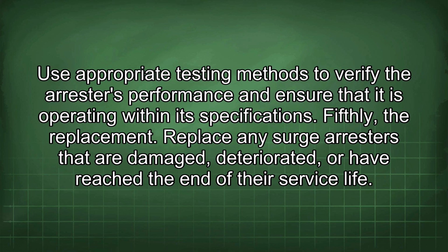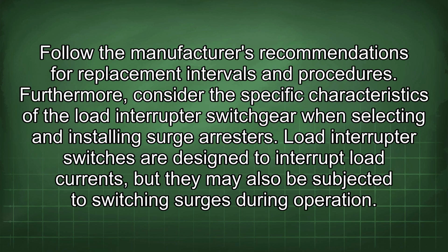Fifthly, the replacement. Replace any surge arrestors that are damaged, deteriorated, or have reached the end of their service life. Follow the manufacturer's recommendations for replacement intervals and procedures. Furthermore, consider the specific characteristics of the load interrupter switchgear when selecting and installing surge arrestors. Load interrupter switches are designed to interrupt load currents, but they may also be subjected to switching surges during operation.